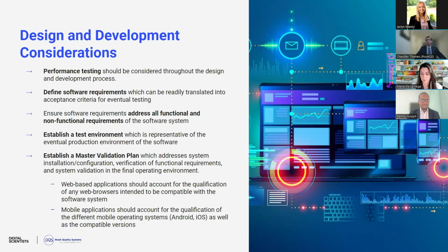So some things to keep in mind is web-based applications should also account for qualification of any web browsers intended to be compatible with a software system. So if you're claiming compatibility with all the big web browsers, whether it's Chrome, Opera, Edge, Firefox, Safari, FDA is going to want to see that you've assessed all of those different systems, you've reviewed the release notes for the different versions of those, you've performed system level testing on each of those systems.